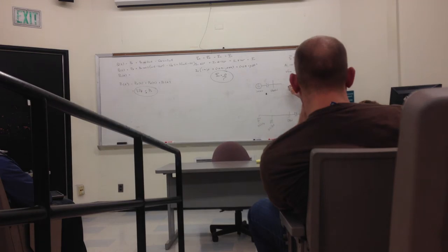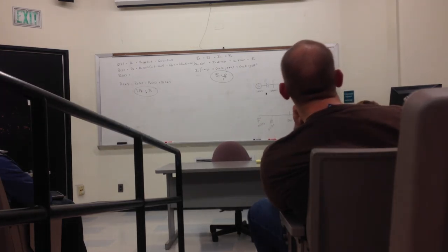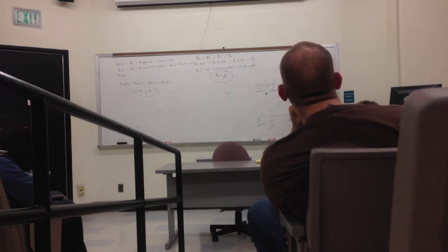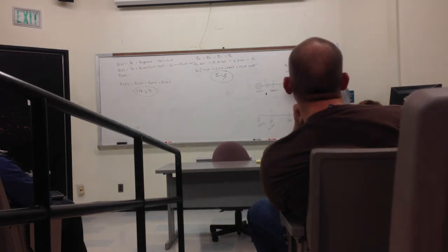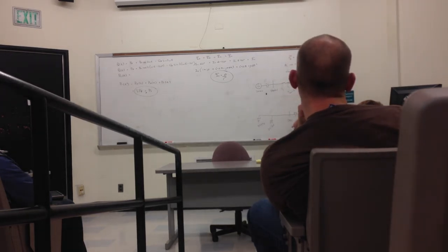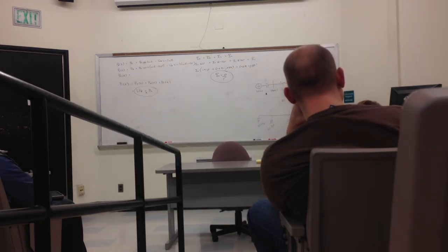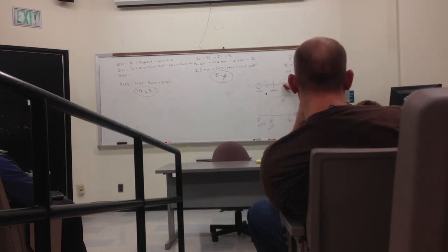So why do we do this? Well, we have two problems inside each one of these transmission lines. We have resistance, from which we get P loss, I squared R. And then from the reactance, more so than the resistance, you have a delta V across here, but it's mostly due to the reactance. This could be 3 to 5 times larger in magnitude than the resistance.